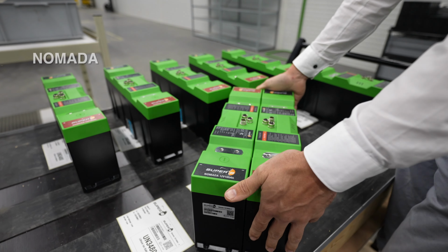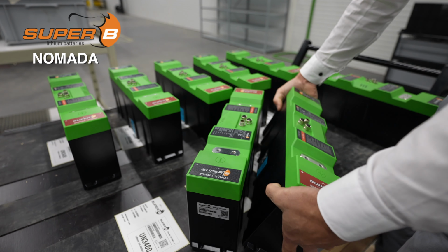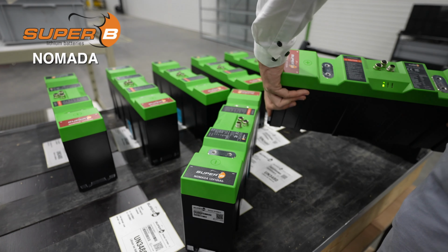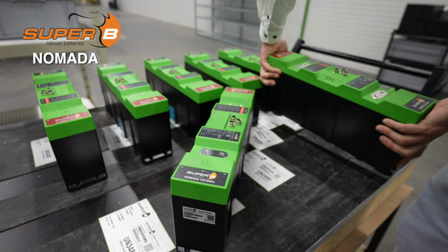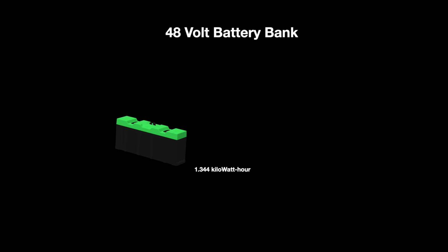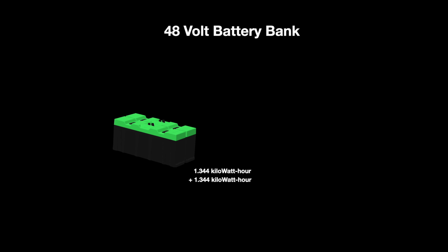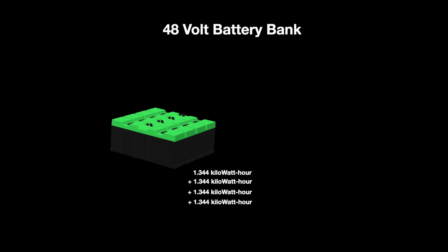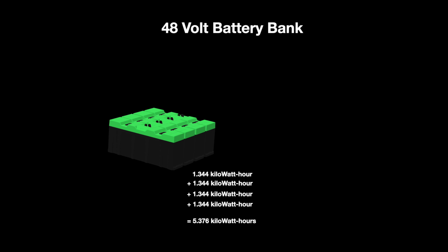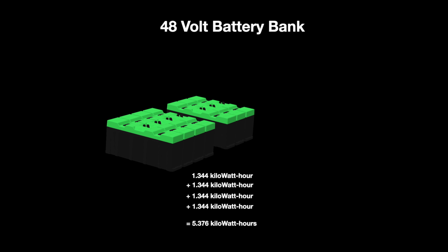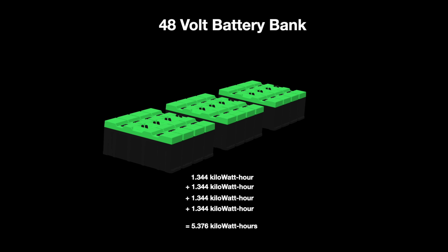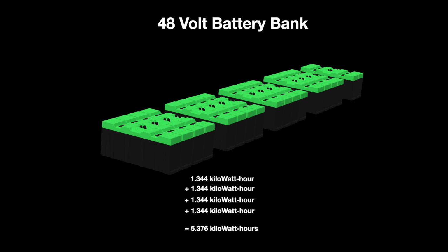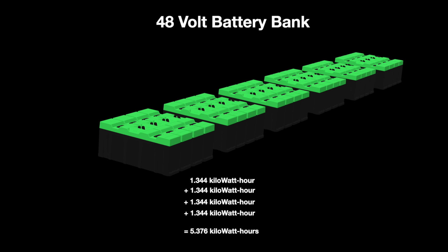These Nomada batteries by SuperB are designed for large systems, and they can be configured to scale up to our planned energy capacity of 30 kilowatt hours. Each battery has a capacity of 1.34 kilowatt hours at 12 volts. Since we need a 48 volt system, we will make up each bank from 4 batteries in series for a total of 5.3 kilowatt hours. Then when we add 5 more banks in parallel, we stay at 48 volts but add energy to get a total of 32 kilowatt hours.